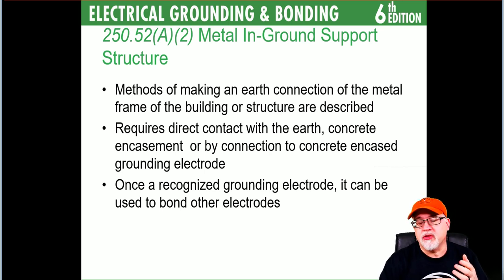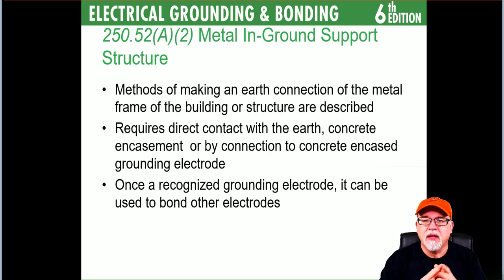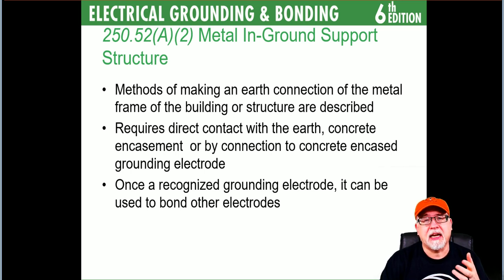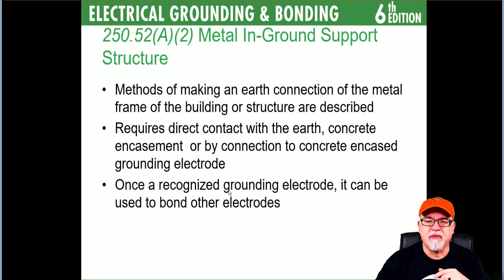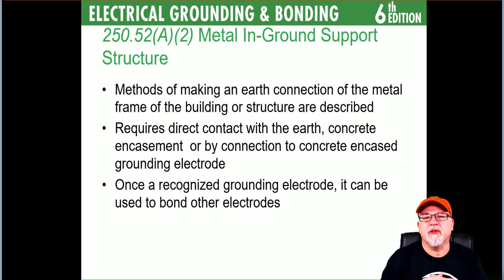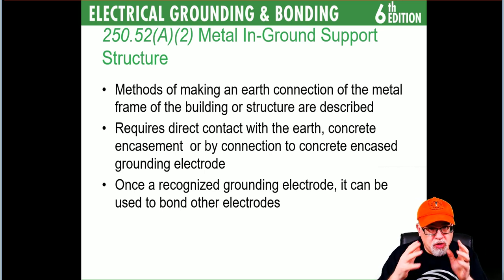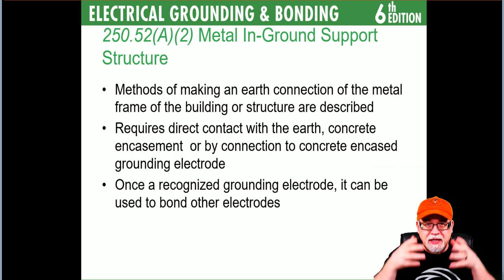250.52(A)(2) is the in-ground support structure — literally the metal framing driven down into the earth. Making a connection to the metal frame of the building requires direct contact with the earth or concrete encasement. Once recognized as a grounding electrode, it can be used to bond other electrodes. There's a lot of surface area in contact with the earth — if a ground rod is acceptable, this metal building support system certainly qualifies.